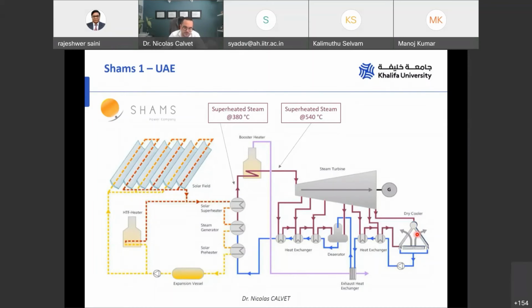And so the quantity of water saved using this dry cooler is 200 million gallons per year, which is 100 times more than what we use to clean the mirror. So just to give you an order of magnitude, cleaning the mirror is manageable. We have 5 trucks working every night using automatic brushes to clean the mirror. And the plant has been performing very well since 2013 without any major problem.